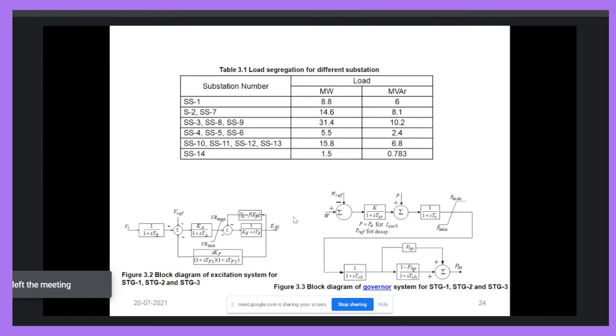Beyond the limit of the governor, the balance will be managed by the load shedding system. If there is a greater amount of connected load, then we have to separate it. We cannot provide that much mechanical power input; it is limited. So whenever there is a huge mismatch between load and generation, we have to separate the load.